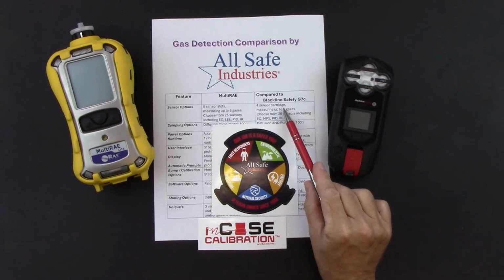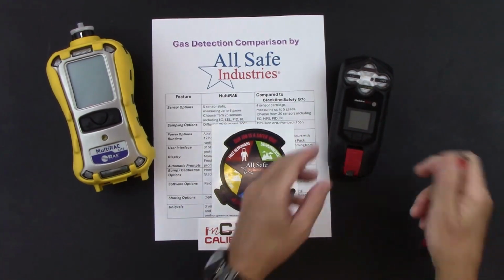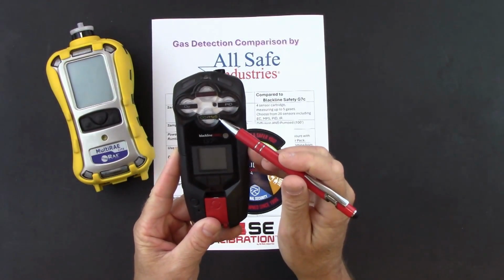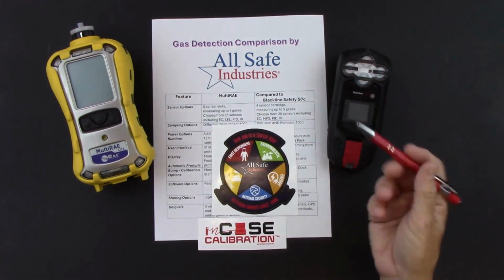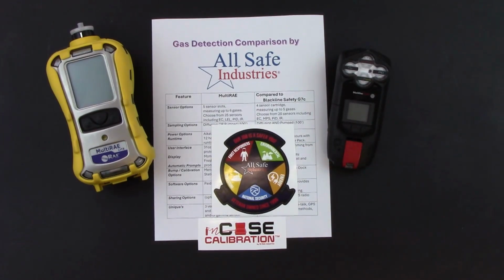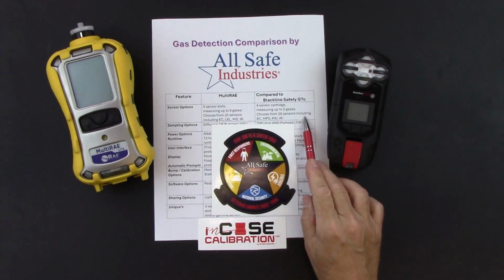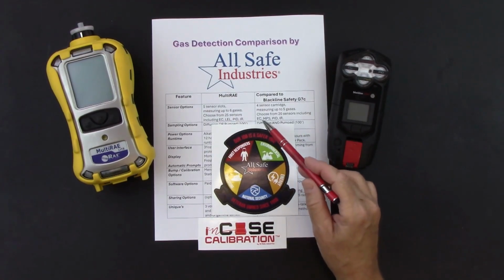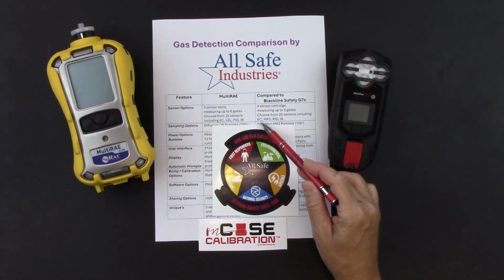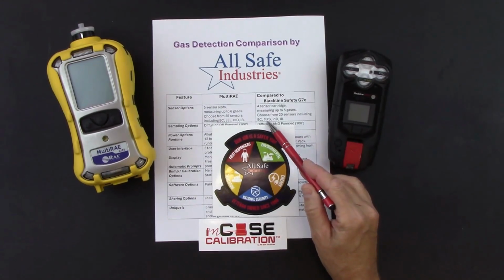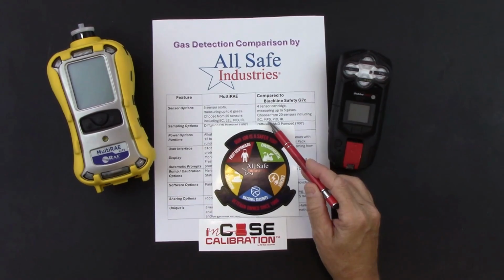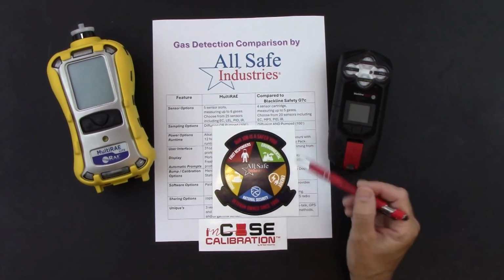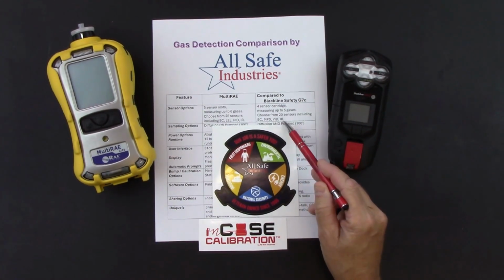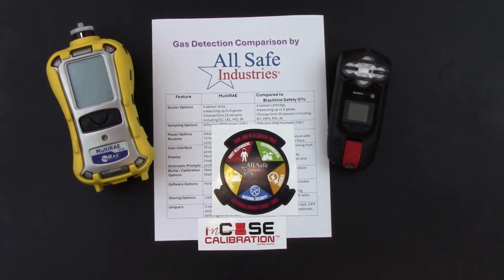So it's a 4-sensor cartridge measuring up to 5 gases. And once again, we can use a CO H2S combination sensor that would get you to 5 if CO and H2S are 2 of the gases that you want in your setup. We have 20 different sensors that we can choose from, and those include electrochemical for oxygen and toxic gases. Blackline Safety uses a MPS LEL sensor, different than a catalytic bead sensor for your combustible flammable gases. We have a PID sensor and an infrared sensor for combustibles and carbon dioxide.